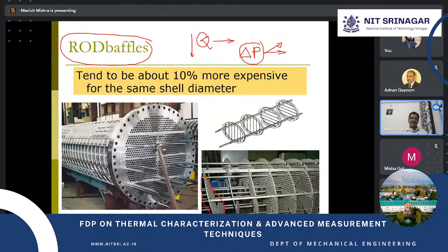Now, whatever is shown on the left-hand side here is not the heat exchanger itself, but basically the tube bundle: all the tubes fixed with the end plate along with the rod baffle kind of things, and the whole tube bundle is now ready for inserting inside the shell. The tubes are not put in individually; this is put inside the shell as a group, and that's why it is called a tube bundle.